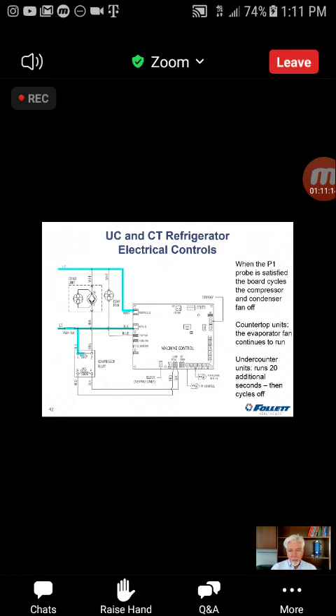Now the countertop units are pure off-cycle defrost. What that means is they have more than enough capacity that there is enough off-cycle time that they will defrost between each run cycle. So it's just running the fan and the ice will melt. If any accumulates on that evaporator, it'll melt naturally during the off cycle.